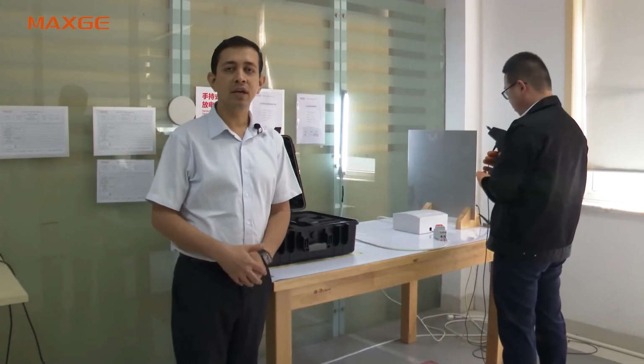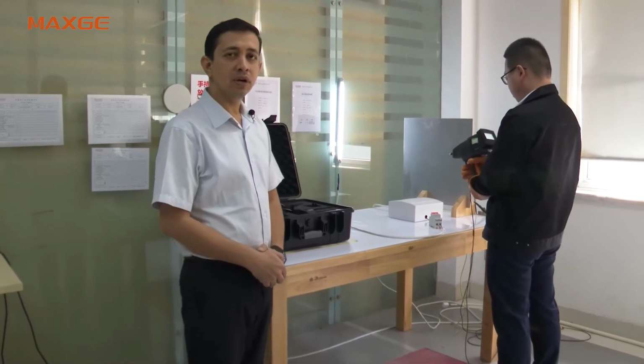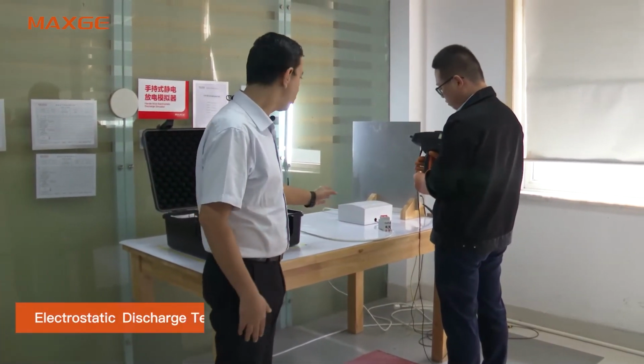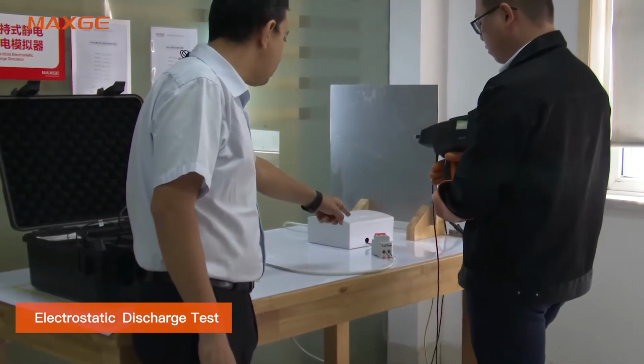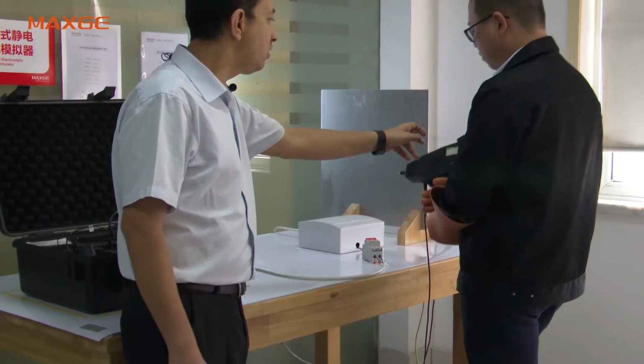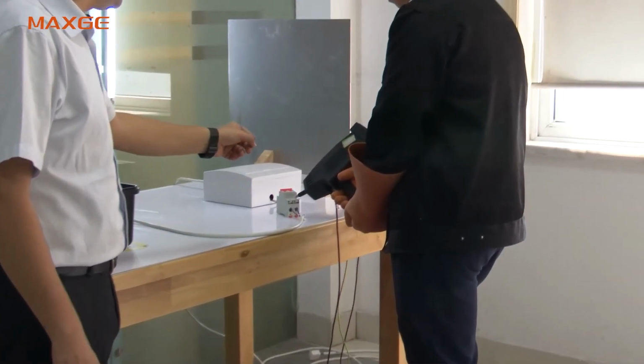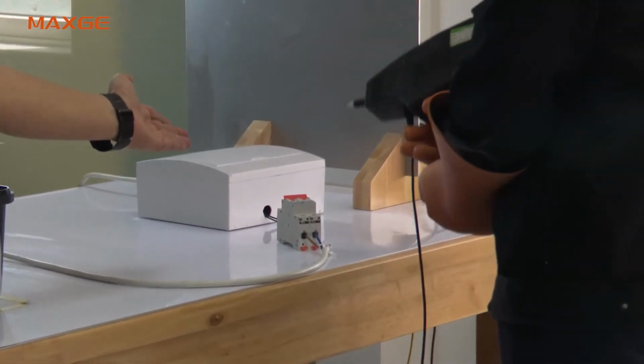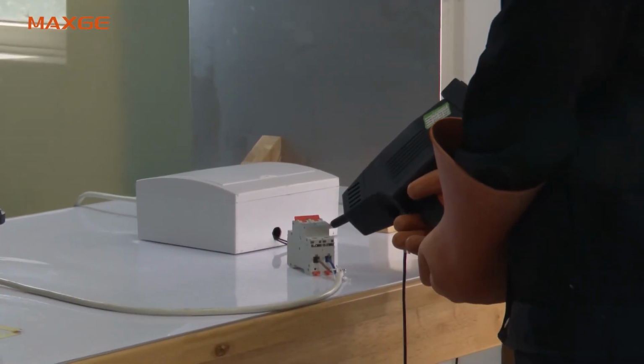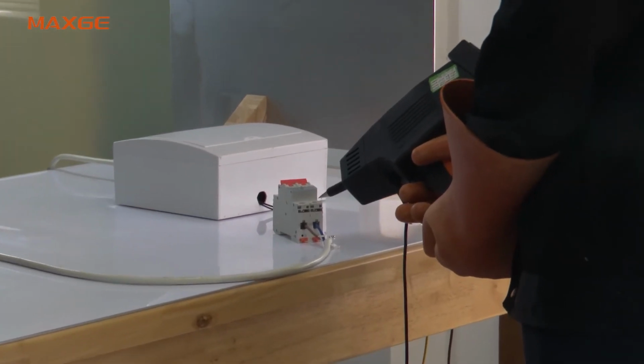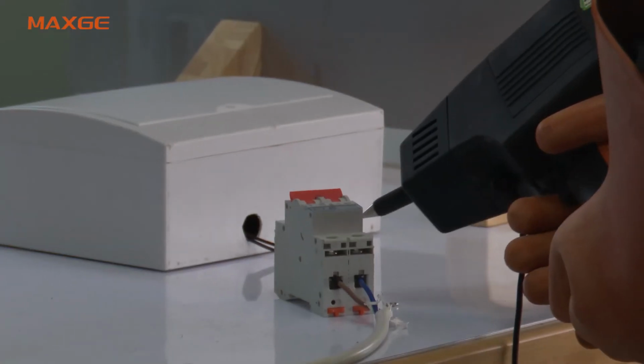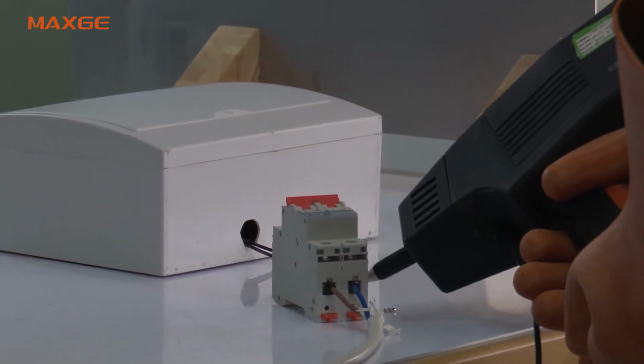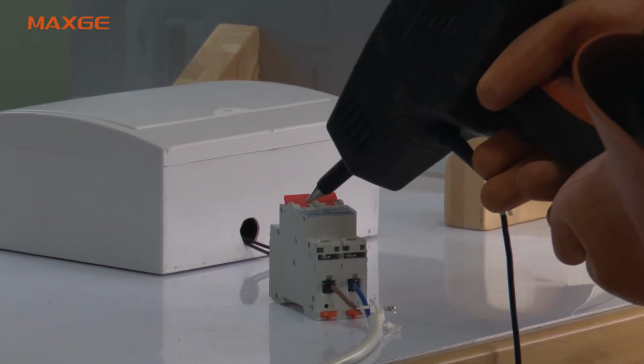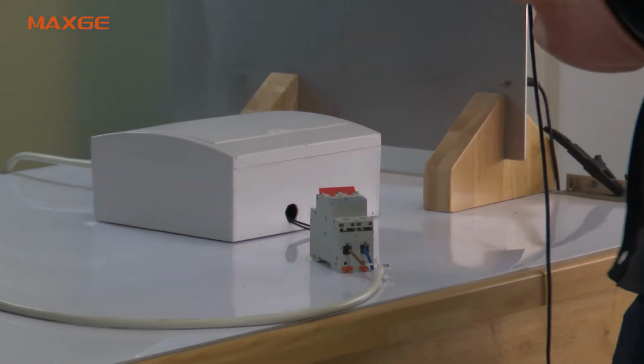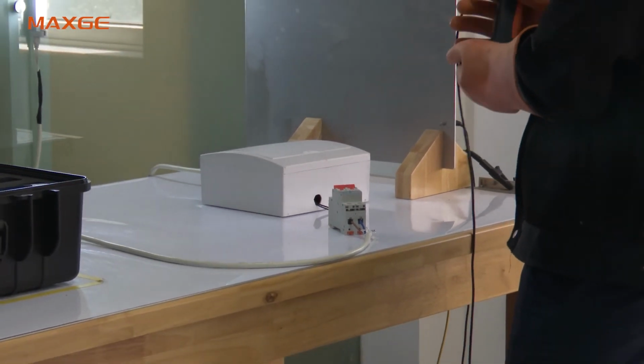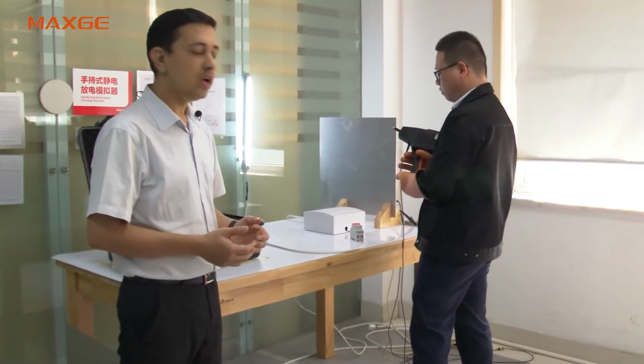Now we are standing inside the EMC test laboratory. Here you can see our engineer is checking the MCB for the EMC test. He has connected the power to the MCB. Now the power is on. Now he is going to apply 6 kilovolts to the surface of the MCB, and he will check whether there is any electrical discharge or not. If it doesn't have any kind of electrical discharge, then the MCB is qualified. If it has some kind of electrical discharge, even a minute one, then the MCB is disqualified.